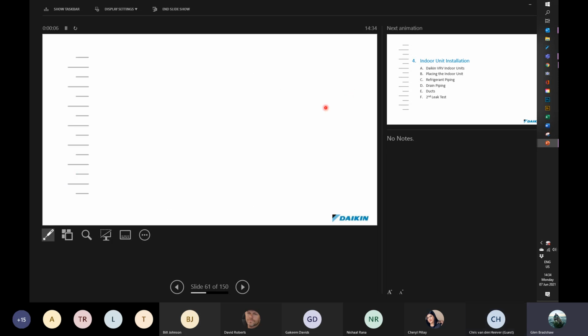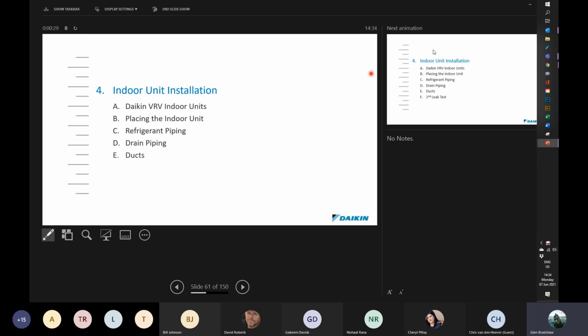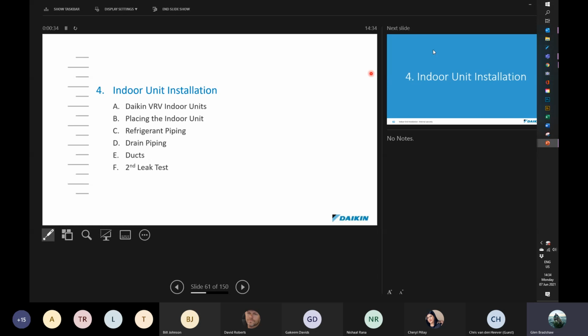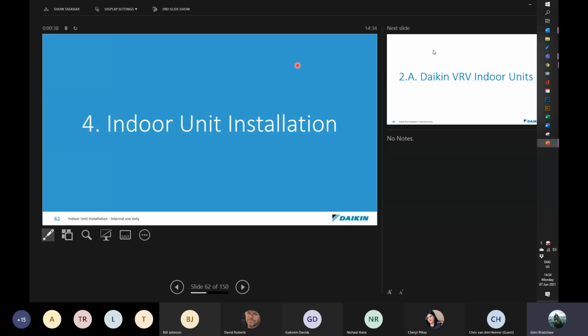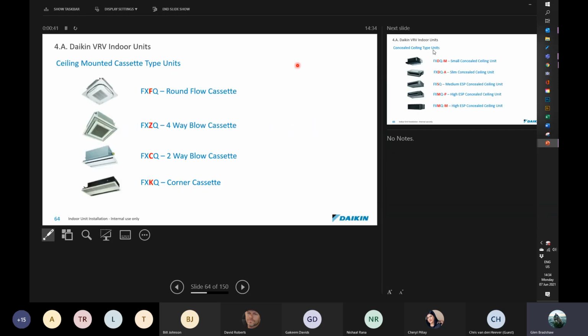All right. So we're going to go into the second part of this afternoon's session, and we're going to look at the indoor unit installation. We're going to look at Daikin VRV indoor units, the types. We're going to look at the placing of the indoor unit, refrigerant piping, just very basic. We're going to cover that in more depth next week. Drain piping, very important. We'll look at a couple of things to remember about ducts. And we're going to look at what we call the second leak test. All right, so indoor unit installation, and let's get on to that.